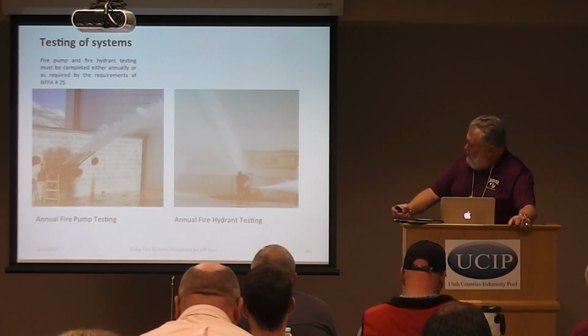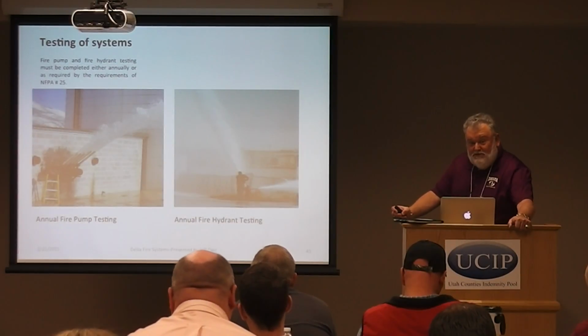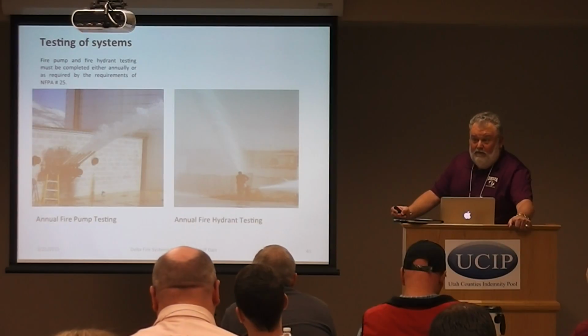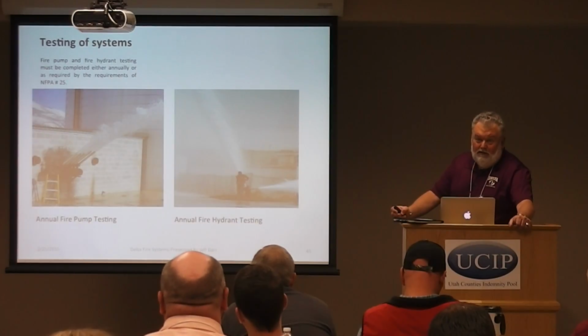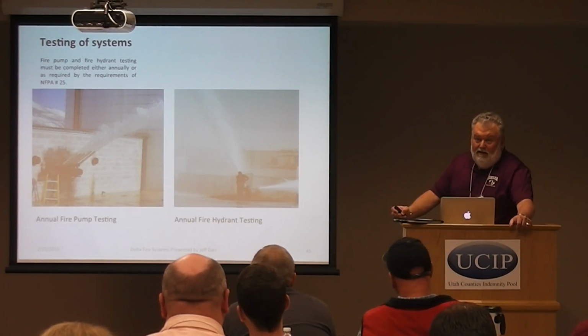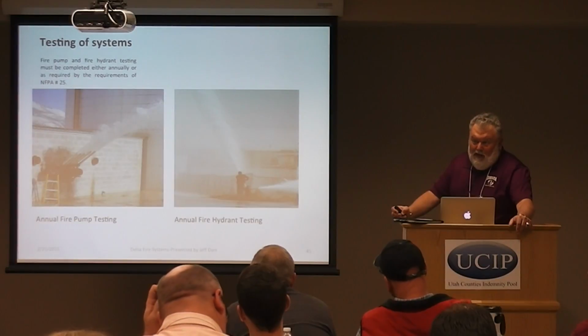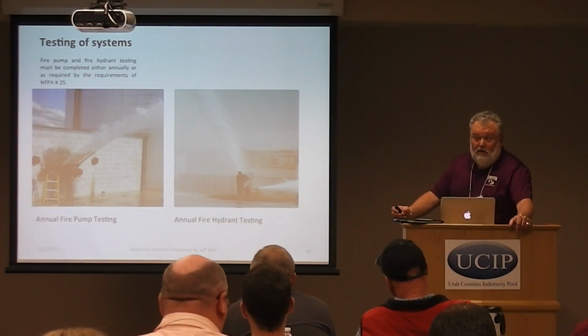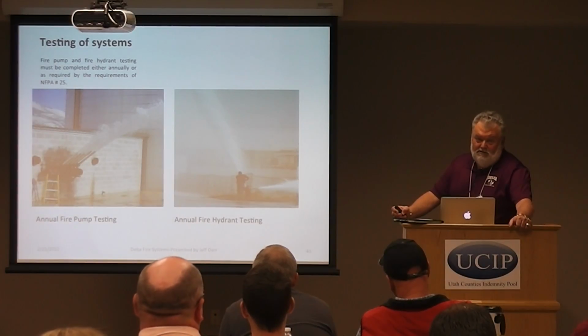The one on the left here is testing the fire pumps. Quite often we find fire pumps over a period of time don't operate near as well as they used to. They may have a rock in an impeller or something, or a valve can be partially closed.